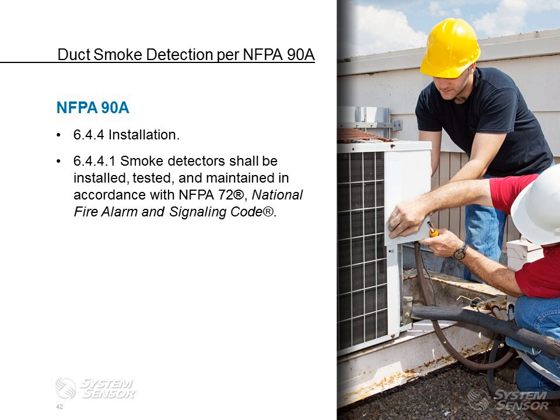Now, if we go back to the International Mechanical Code that we talked about, they reference duct smoke detectors being used in accordance with the fire alarm system for the International Fire Code. Well, the International Fire Code also references NFPA 72 for testing, maintenance, and installation. I know it's kind of convoluted and kind of confusing. At the end of the day, both of the standards, whether it's a direct route or kind of a roundabout way, are saying that installation, testing, and maintenance need to comply with the NFPA 72 standards.